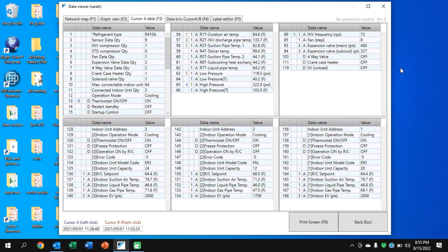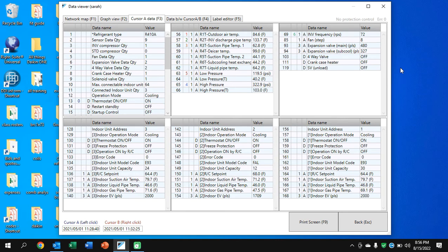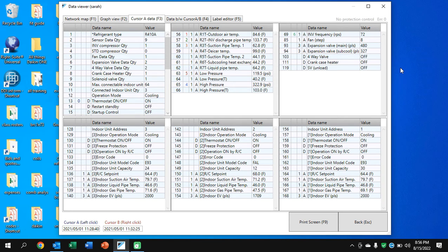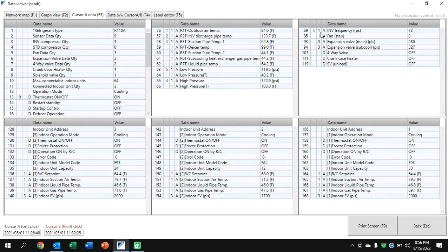But I want to look at the indoor EV pulses. And you'll see these are 2,000 pulses. And so all three of these heads are open. If I had one at zero, it would be an unopened head. And if that is zero, I should not see a temperature drop. And if I do, it's robbing some refrigerant cooling or subcooling effect from the other units. We can run the fan, look for delta T. And we should not have a delta T when our EV shows zero. Otherwise, we know it's stuck open.